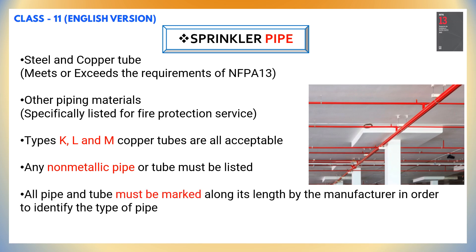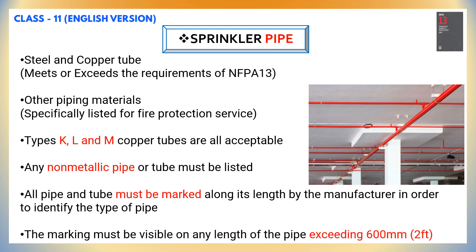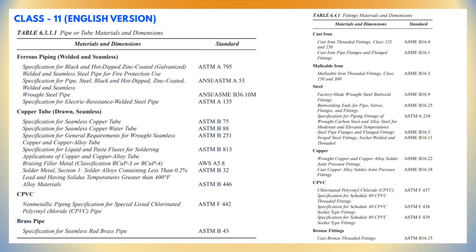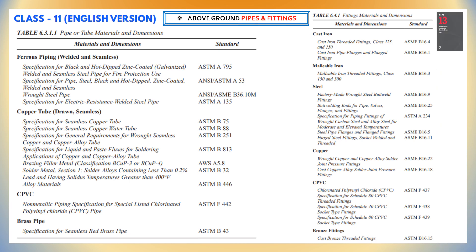All pipes, including specially listed pipes allowed by NFPA 13, shall be marked along their length by the manufacturer in such a way as to properly identify the type of pipe. The marking must be visible on every piece of pipe over 2 feet or exceeding 600 mm. Pipe identification shall include the manufacturer's name, model, designation, or schedule of the pipe.